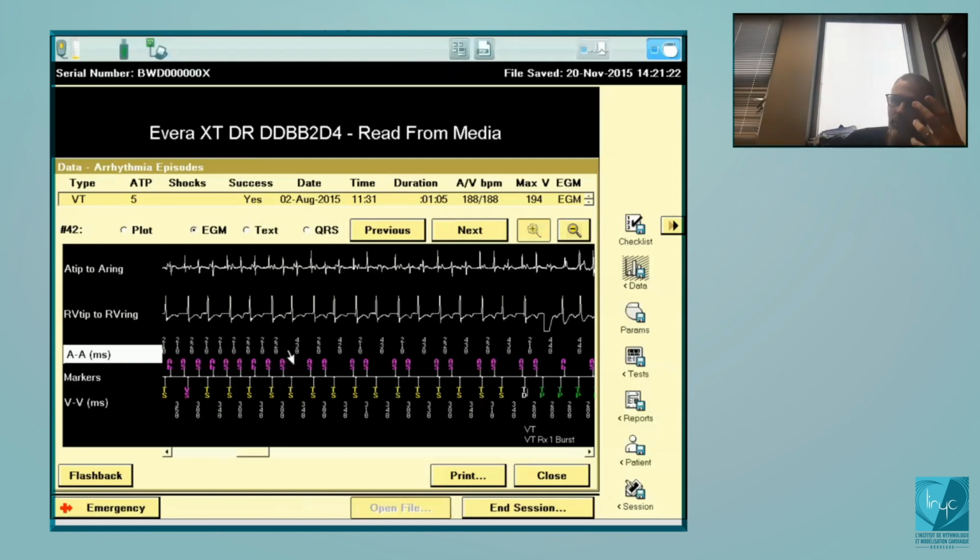And therefore, for the diagnosis of the PR logic, that's going to be a VT, okay, without further analysis. And remember, that's a choice. Always you have to make some choices for the manufacturers. But if the device says, okay, ventricular rate faster than the atrial rate, there is no possibility of correction with the wavelets.